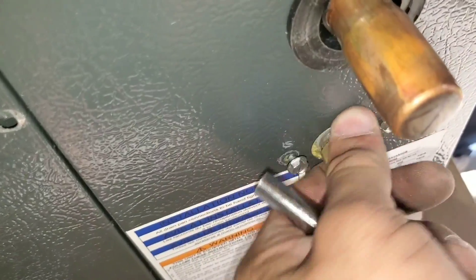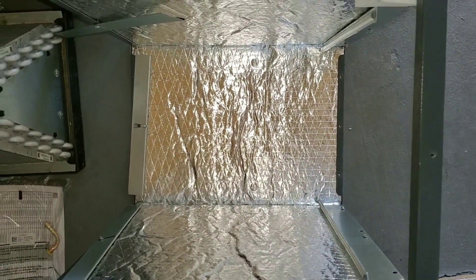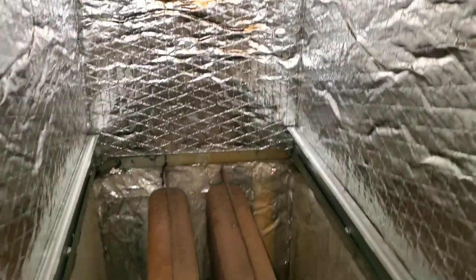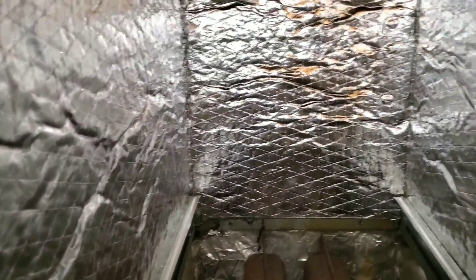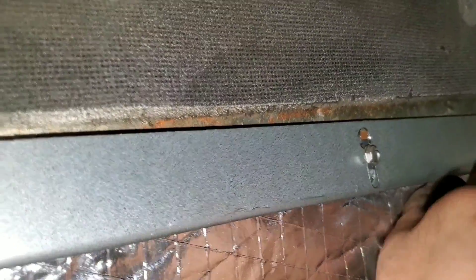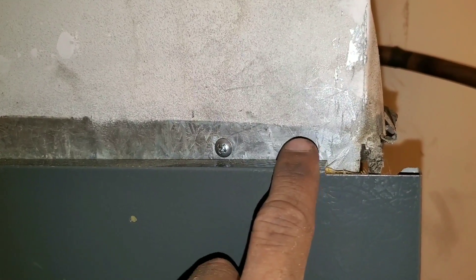Remove the front panel for your evap. Loosen the nut for your high side. Slide out the old evap coil and put it to the side. Dry fit your frame — you want to ensure that it fits nice and snug. It is possible that you may have to do some alterations and cut the ductwork. You really don't want any major gaps between the ductwork and the frame. Secure the ductwork to the frame.